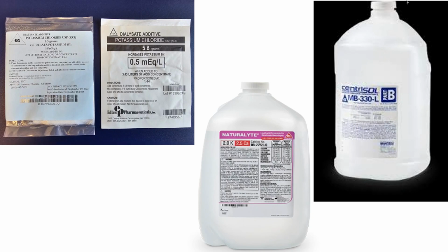So in that configuration, a slight, simple reduction of any of those components, change of component, will highly affect your conductivity because it's such a small volume. If it was a large volume, a slight change wouldn't matter. But being such a small volume for flow, it does change that. And a lot of things will change your concentration, and I'll show you some of that.